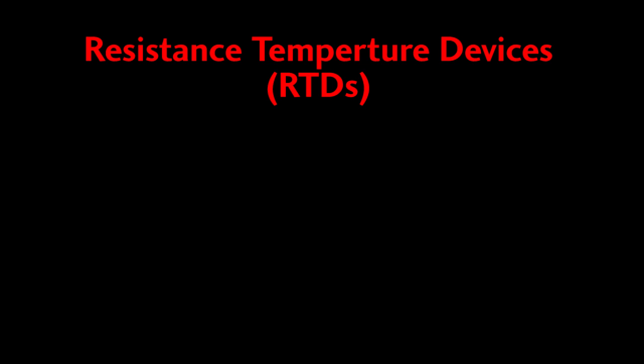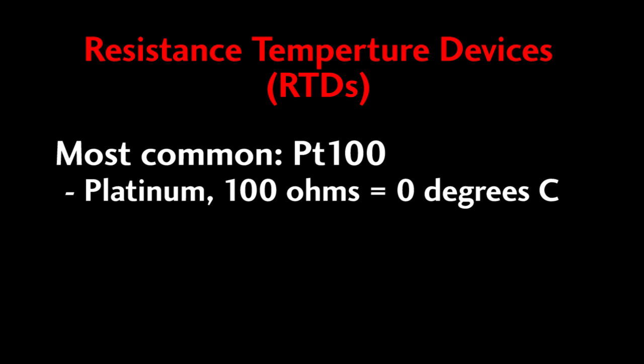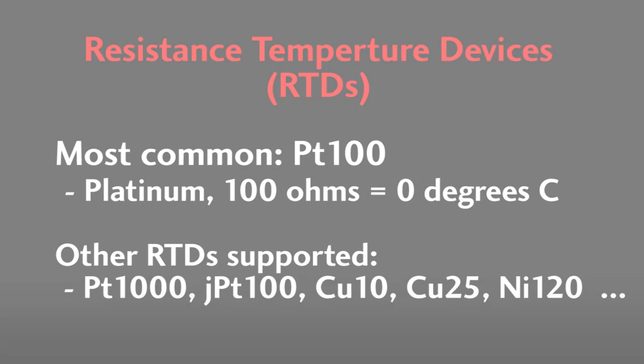RTDs come in a variety of types with the most common being a PT100. It is made from platinum and has been calibrated to be 100 ohms at 0 degrees C. AutomationDirect's PLCs handle a wide variety of RTDs including PT1000s, JPT100s, CU10s, CU25s, and NI120 just to name a few.